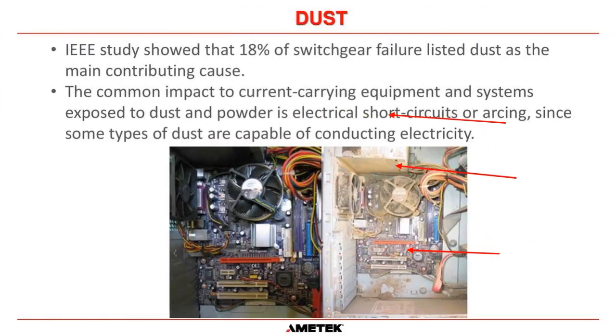So the next failure mode is dust. An IEEE study showed that 18% of switchgear failures listed dust as the main contributing cause. Okay, 18%. Now, I didn't have any information for UPSs, but I'm guessing it would be relatively similar. And the common impact to current carrying equipment and systems which are exposed to dust is short circuits and arcs.